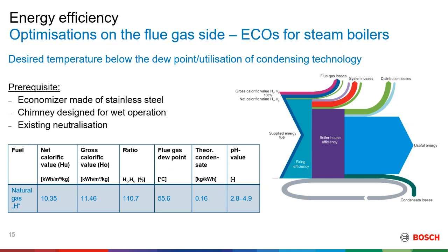I know it's a big problem, especially for sites where you have raw, very cold water flowing into the economizer, which causes condensation. So for Bosch, we have a preheater between the economizer and the feed water tank.